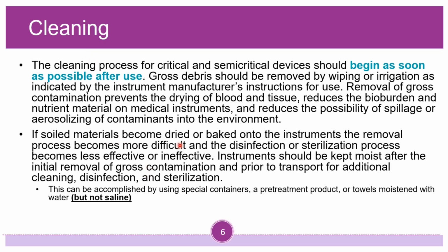If soiled materials become dried or baked onto the instruments, the removal process becomes more difficult and the disinfection or sterilization process becomes less effective or ineffective. Instruments should be kept moist after the initial removal of gross contamination and prior to transport for additional cleaning, disinfection, and sterilization. Another reason why it's really important to spend time in SPD in your ORs is because you're going to have procedures that vary in length.